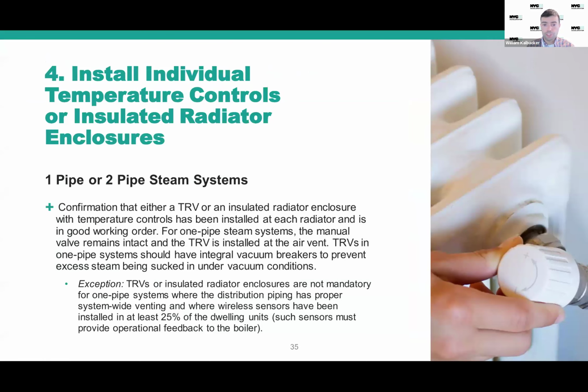Just a little bit more information here regarding TRVs. So specifically for 1 and 2 pipe steam systems, the TRV is a little device that you can install on the radiator itself to ensure that the unit is not overheating the space. And there is an exception here. So for 1 pipe systems that have proper venting, and we'll discuss venting in a little bit, and where there are wireless sensors that have been installed in at least 25% of the apartments that are providing feedback to the boiler controls, then this is not required. But for all others, individual unit heater controls are required.